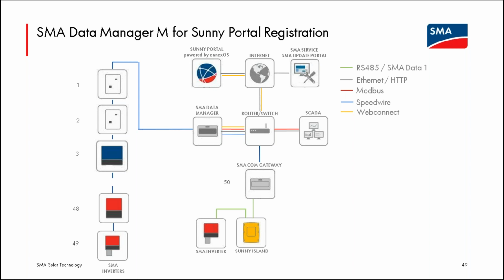So currently, it requires both of these devices to register a system with SMA inverters and the Sunny Island US to the portal. Very shortly, I believe next quarter, there is an RS-485 port on the data manager that will be supporting SMA's RS-485. When that occurs, the COM gateway requirement goes away. You're down to one device that is required to register all of these SMA inverters to the Sunny Portal. We'll definitely make a lot of noise about that when it occurs, but it should be a few months out at most. So that is the real pain point, I think, now, is sending all of this data to Sunny Portal. There is free software from SMA that allows local monitoring directly through the COM gateway.